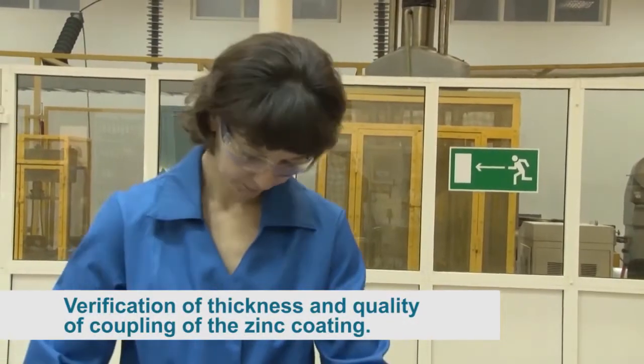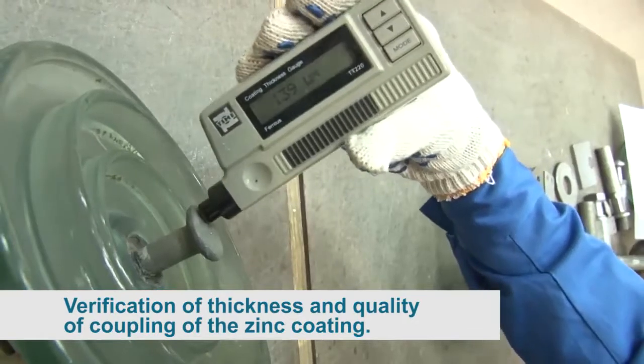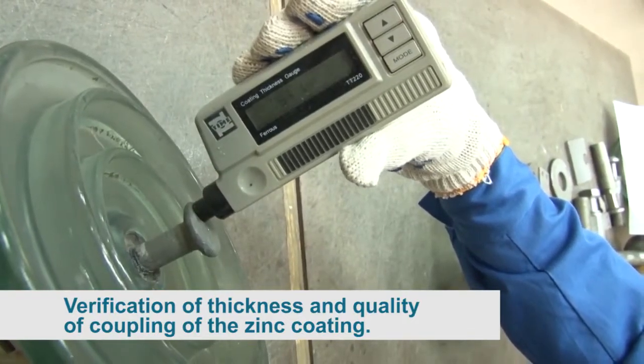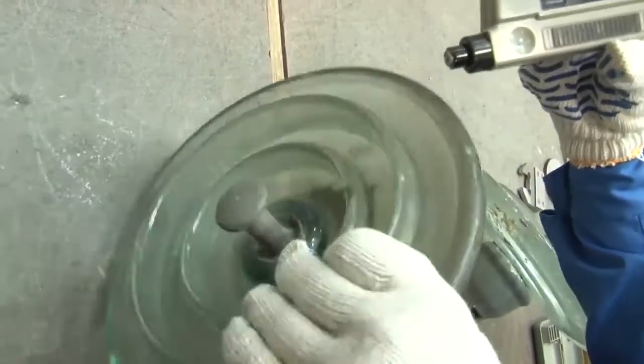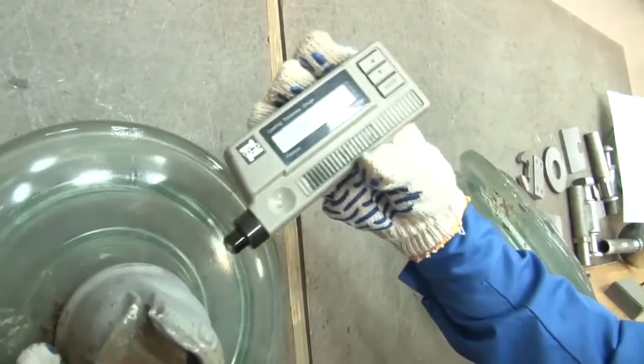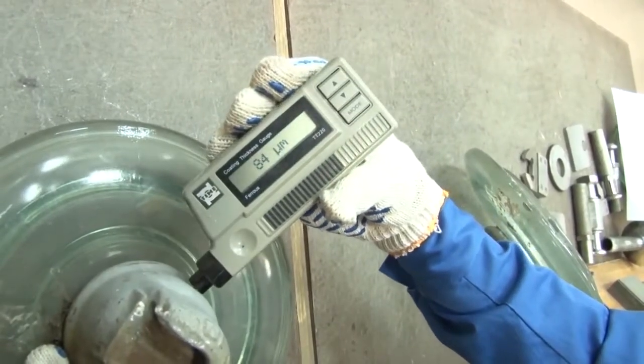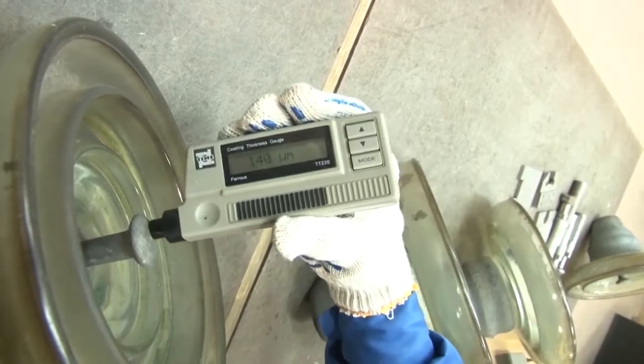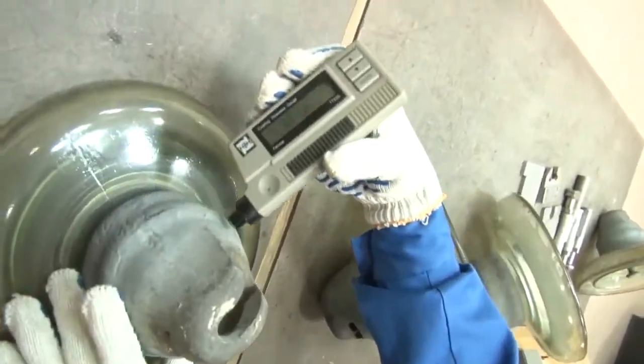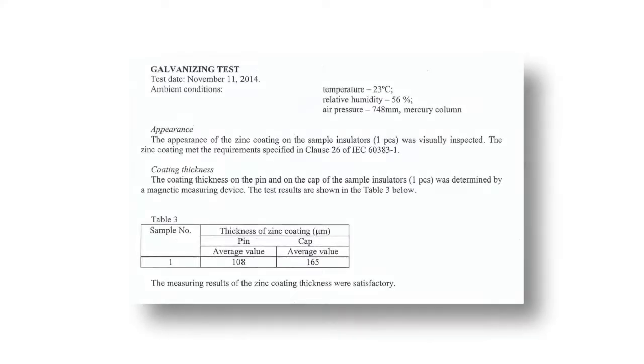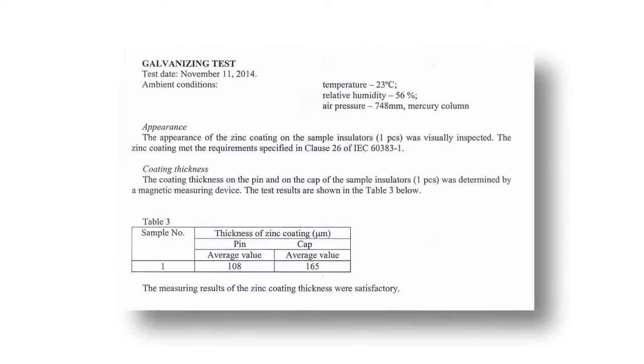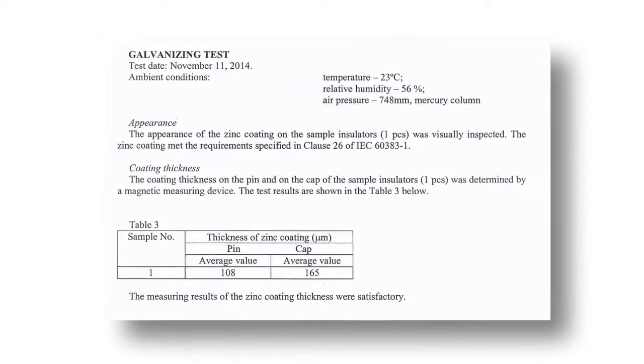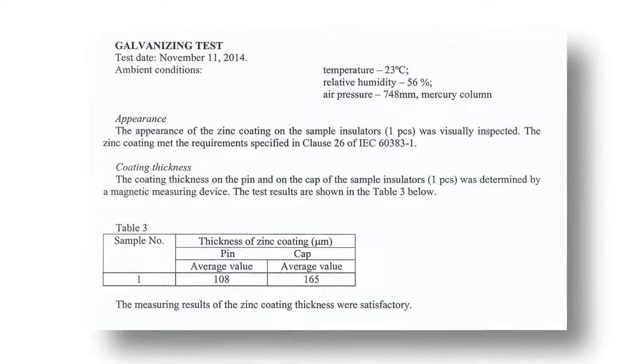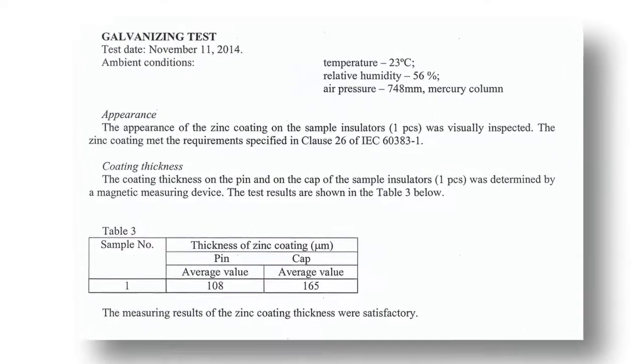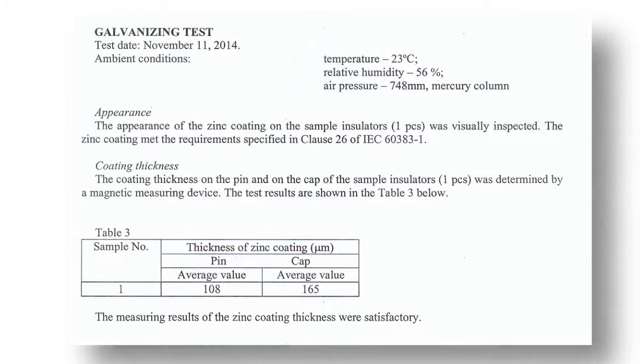Verification of thickness and quality of coupling of the zinc coating of the PS12A insulator. Thickness of the zinc coating of the pin, 101 to 110 microns, cap, 127 to 182 microns. Verification of the quality of zinc coating of the insulator of PS70E, the pin, 108 microns, the cap, 165 microns. Insulators meet the IEC requirements.